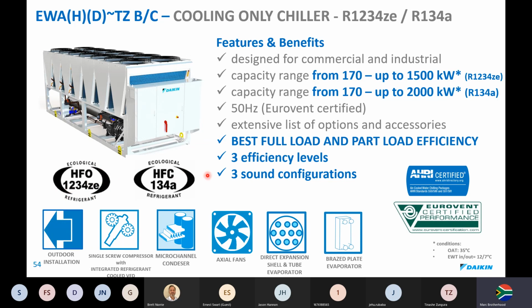Whereas 134A, you're looking at probably about 1200 global warming potential. But there's still a lot more energy in R134A. When I say energy, heat transfer capability, so we can cool up to 2 megawatts if you select 134A. We derate the chillers if we're using the more ecologically friendly refrigerant, because it's less environmentally damaging, but it doesn't have the best thermodynamic capabilities like the R134A.